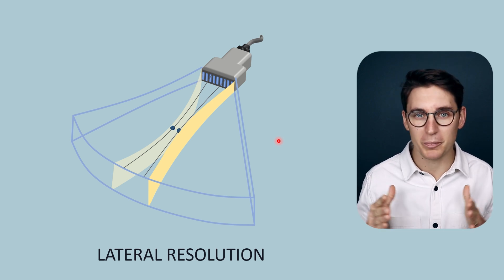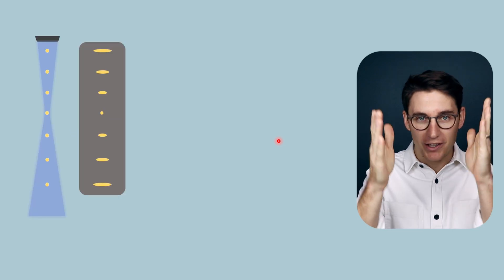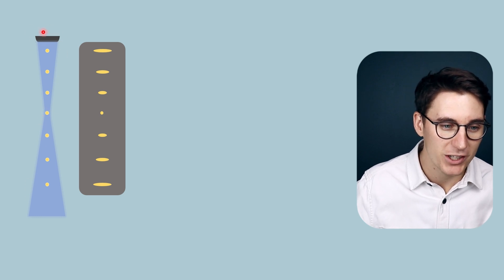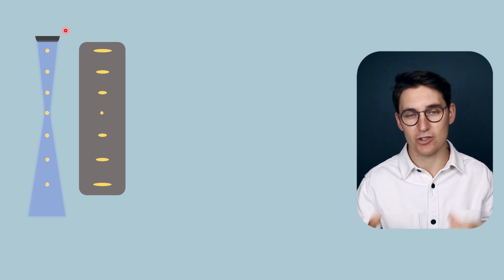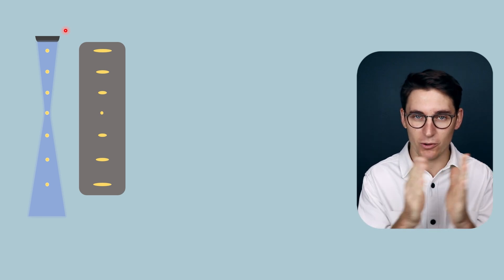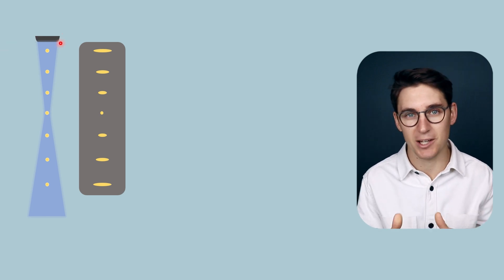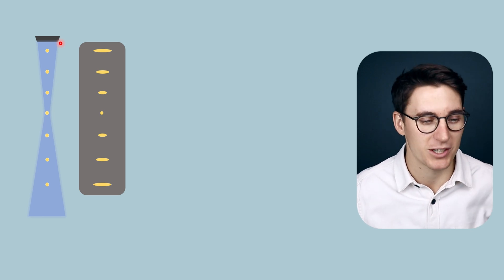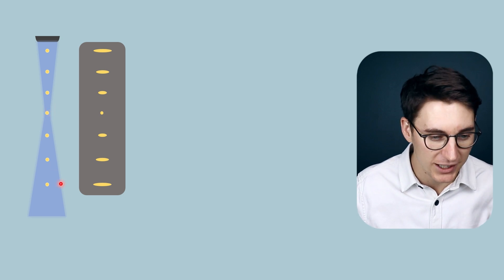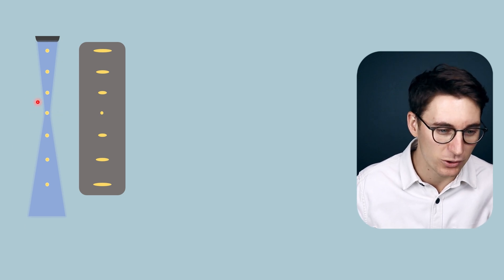Lateral resolution relies heavily on beam geometry and beam focusing, both of which we've covered in previous talks. If we look at an ultrasound beam heading into tissue — this blue beam here coming from a discrete group of transducer elements — these elements either cover the entire face of our transducer or are groups fired off separately in linear arrays. This beam naturally converges to a focal point and then diverges in the far field. We have a near field, a far field, and a focal zone.